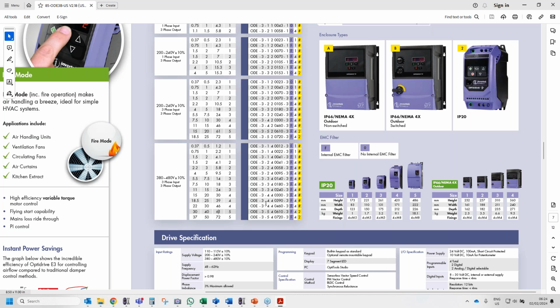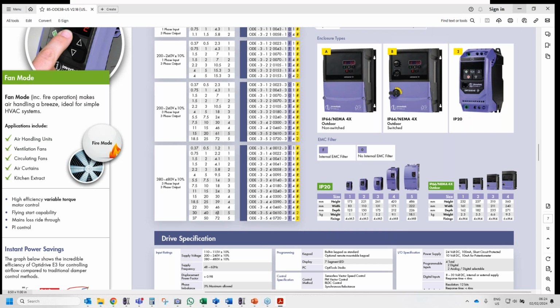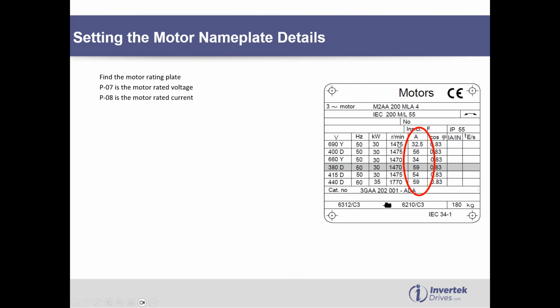Yeah. And of course, the higher the voltage, the lower the current per kilowatt. So you can see here, a 380 volt, 30 kilowatt is 59 amp, 400 volt, 30 kilowatt, 56. 415 is what we have here in Australia, that's 54 amp. So these are the real numbers, these are calculated numbers. So always use the real numbers.